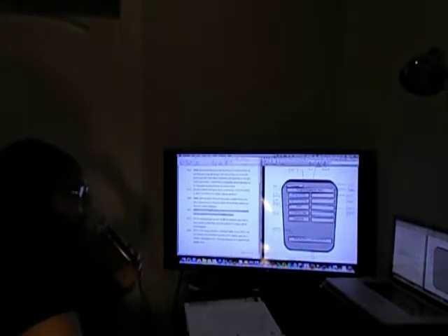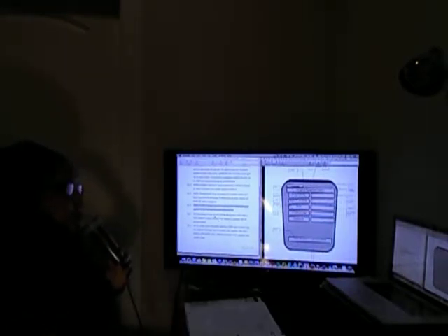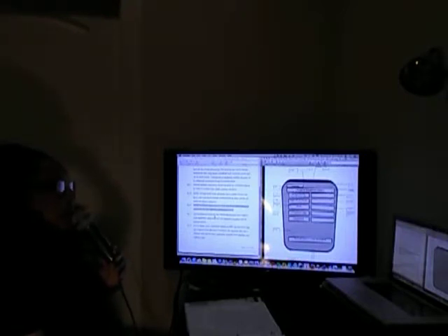So we would like to have at least a 24-hour turnover period. Some things can be turned over in 8 to 12 hours. Some require 24 hours, depending on the procedure, especially if you're using an autoclave or sending something through the wash and it needs to air dry.